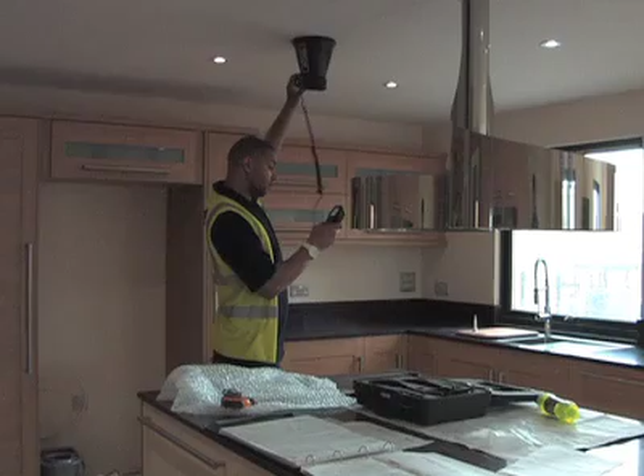Once the system has been installed, it must be set up to meet the design flow rates using an anemometer with a Venturi cone fitted to check and set the flow rate at each extract and supply valve.